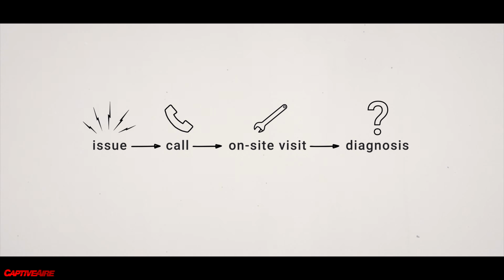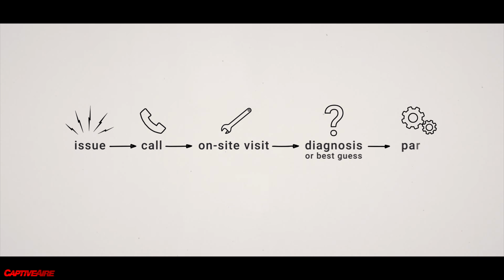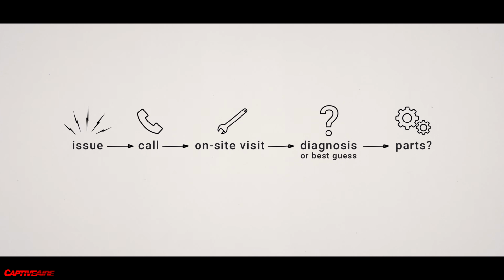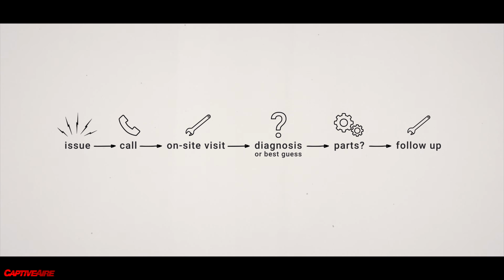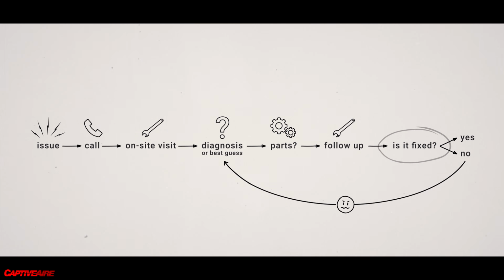There's a chance that they'll figure out what it is on site. There's a chance that they won't, and they might have to go with the most probable issue based off of whatever fault code they see. They may or may not have that part on hand. If they don't, you have to call, order up a part, wait for that to come in, set up a follow-up visit, change that part, and then just see if the system's repaired and if it works.